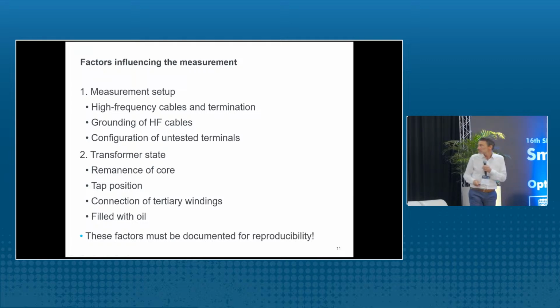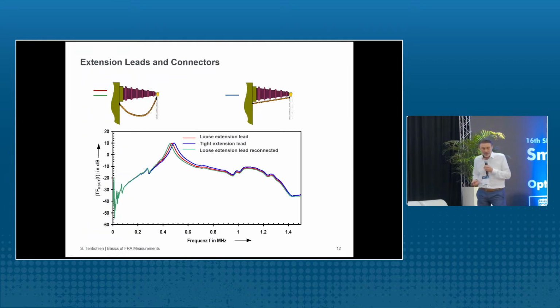I will not explain all these, but maybe I can show one thing, which is this connection from the tank to the cable, this grounding connection. Here we have a grounding cable which is not directly parallel to the bushing like here, but it's just freely hanging under the bushing. And of course, if you have such a loop, such a loop means an inductance. And an inductance, of course, influences the frequency spectrum.